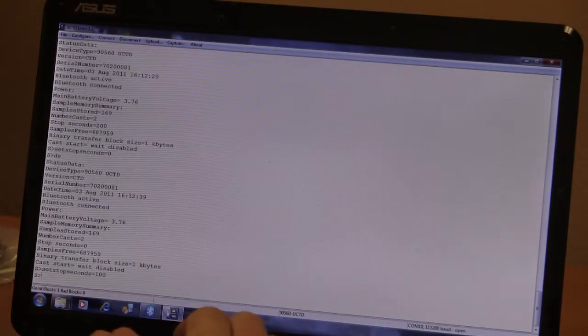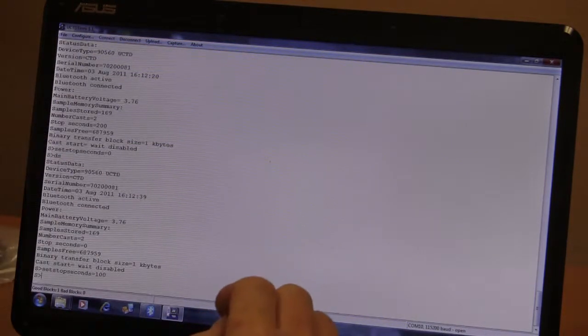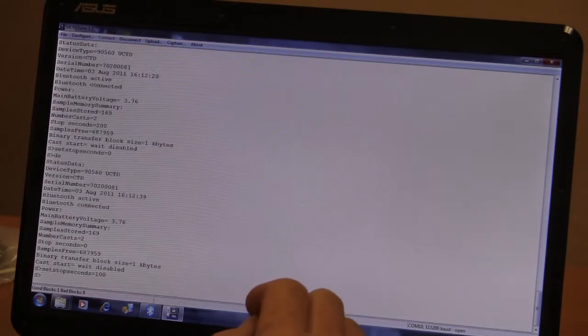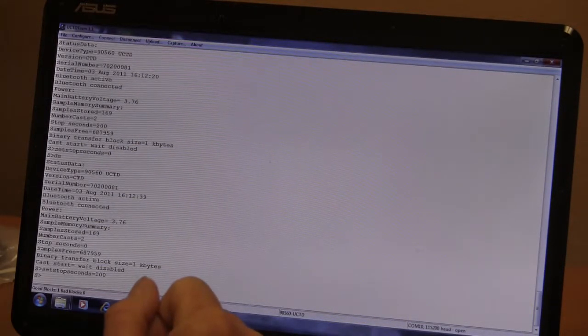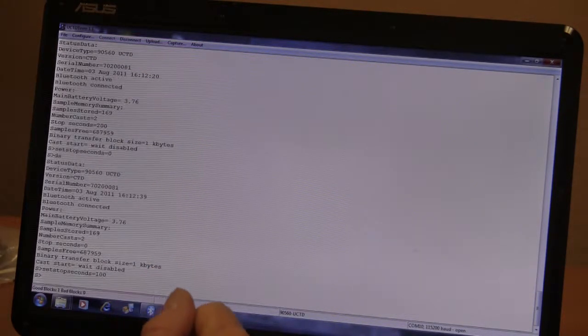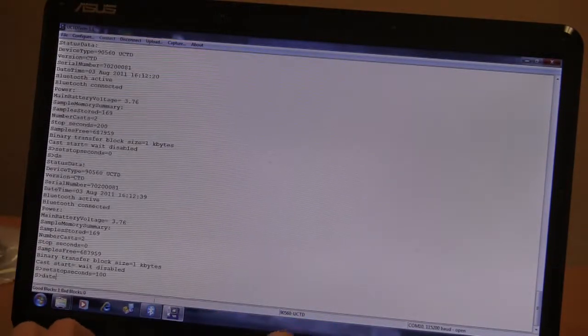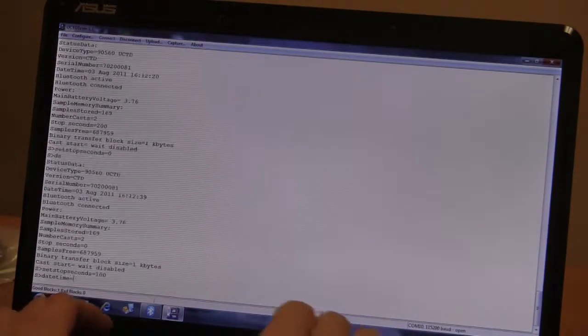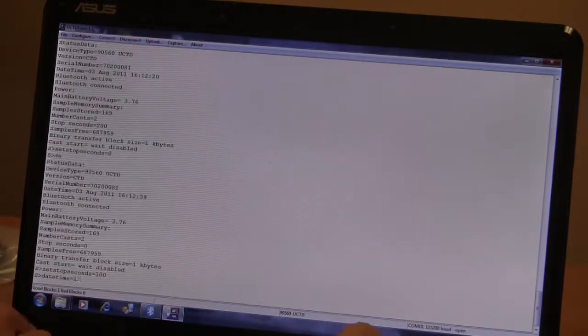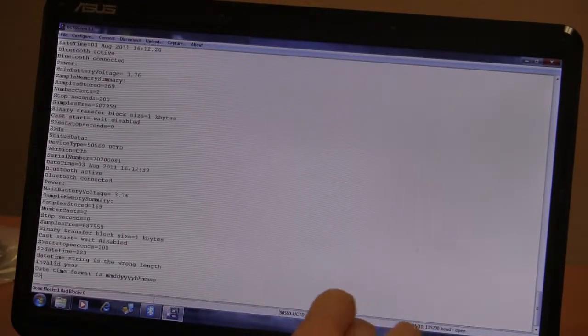Now, if we want to synchronize the probe clock with the GPS clock, the thing you have to do is set the clock on the probe to whatever time zone you use. In this case, typically it's Greenwich Mean Time, to synchronize it with the GPS. The way you do it is date time equals, and since I can never remember the syntax of that command, I just press 1, 2, 3, and it's going to complain that I entered the wrong format. But now it actually gives you information about what the correct format should be.